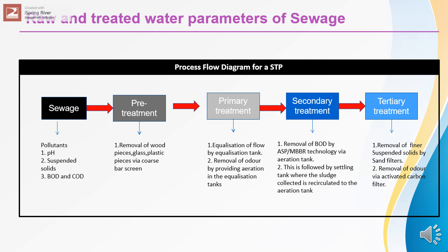After the BOD is removed, it moves to the clarifier wherein the sludge settles down and the clarified water is pumped to the tertiary treatment system. The tertiary treatment system constitutes a pressure sand filter, which filters the fine suspended solids, and activated carbon, which removes odor by the process of adsorption.